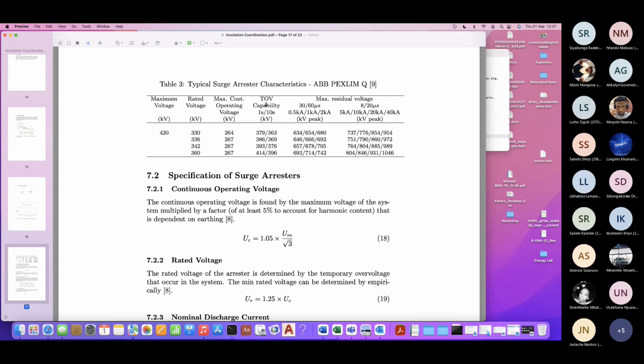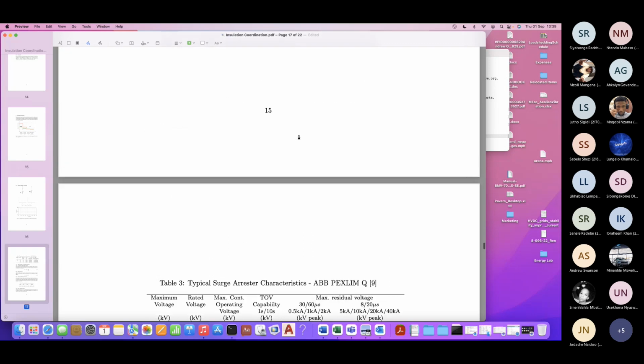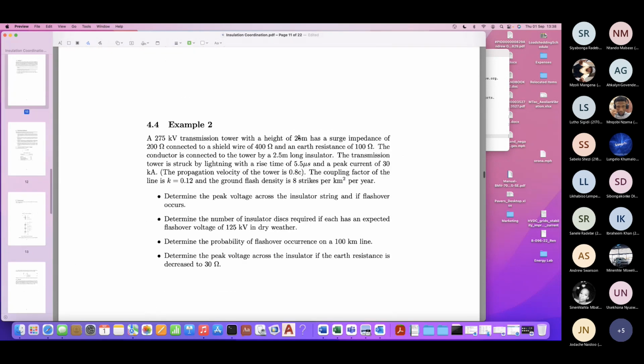There are some characteristics. Temporary overvoltage capability, TOV, it does give some ratings, and you can see that they're slightly higher than the rated voltage or maximum continuous operating voltage. Then your maximum residual voltage, and it gives various voltages. So 634 for 0.5 kiloamp, 30 by 60 microsecond waveform. So that's the peak of the overvoltage. You can see that it's limited at, let's just note that, 737, and we're going to go back to the table just now.